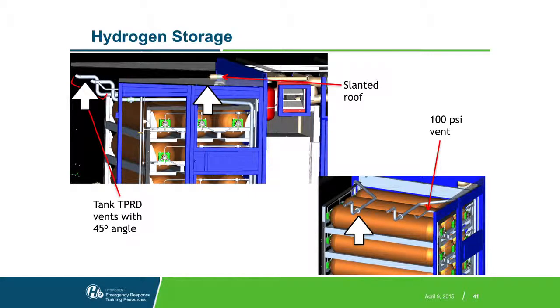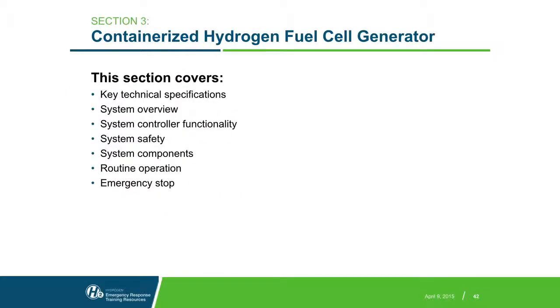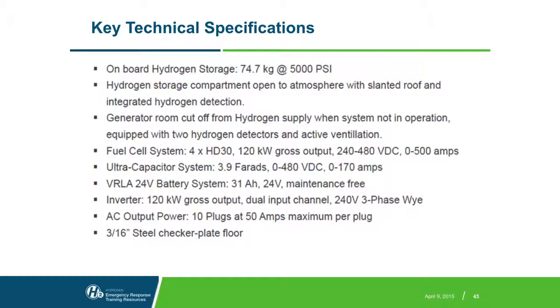Okay? This is also essentially open to air, so there's a lot of passive ventilation in this end of the ISO container. It's not a sealed container on this end. This is the vent for the low pressure line that delivers the hydrogen from the tanks to the fuel cell. So there's also a vent for that line. Again, we're storing almost 75 kilograms of gaseous hydrogen at 5,000 psi. Also, this hydrogen storage is open to atmosphere, and we have that slanted roof.